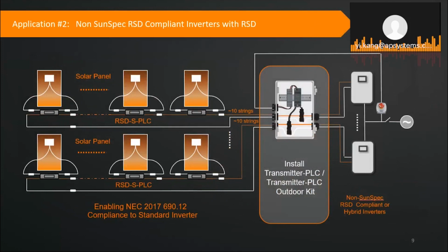All right, so application 2, like we said, if you have a non-SunSpec certified inverter, you're going to use the outdoor case package. That's how you wire them out. You take the wire from the grid input side after it gets to the breaker. Then use the AC to power your AC/DC power supply and power your transmitter here. You can also put more than one inverter, but that is mainly for commercial jobs. Normally, one inverter is good enough for residential.